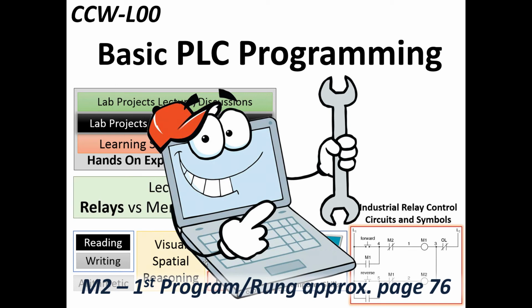Always remember, there is no such thing as an online program. There are only offline programs, and when you go online, you're taking the data out of the controller's memory and you're using it to animate the ladder logic diagrams that you're looking at on your screen.